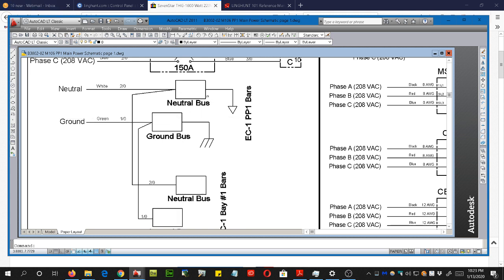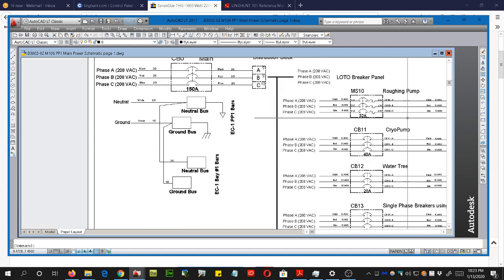And we had one machine that was headed off to Germany, and up underneath the cabinet where you can't see, one of these little neutral wires, like a 20 gauge or something, got put over on here, and we had like 4 milliamps or something on the ground, and the dude was like, "No, you're screwed. We can't ship it till you fix it." You know, you're like, "Well, how in the hell am I going to find that?" So we dug around and we worked, and we found the wire was off. And once we moved it to the right spot, it was perfect. So I was like, "Damn, I guess I'm good."